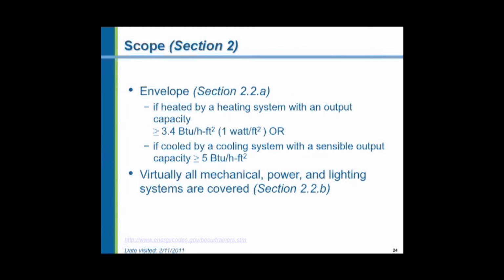Less than 1 watt per square foot, which equates to 3.4 BTUs per hour per square foot. So if you heat the building less than that, the code does not apply. Or if you cool and air condition a building less than 5 BTUs per hour per square foot, the code does not apply. So minimally heated or minimally cooled buildings are not covered. But even though the building envelope may not be required to comply with the new energy code, the systems in the building must: the heating, air conditioning, and plumbing systems.